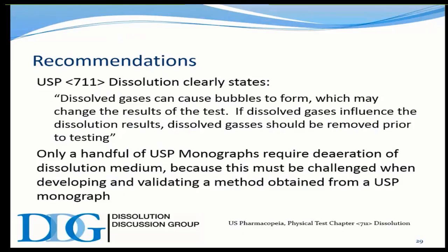directly from the dissolution chapter, which is harmonized with the European and the Japanese pharmacopoeia, that dissolved gases can cause bubbles to form, which change the results of the test. If dissolved gases influence the dissolution results, dissolved gases should be removed prior to testing. Very interestingly, there's only a handful of monographs that say anything about deaeration. Now, why is that? Well, that's because of the statement that's in 711. That's the one that verifies that you've challenged that method, and if it is affected by dissolved gases, it's removed.